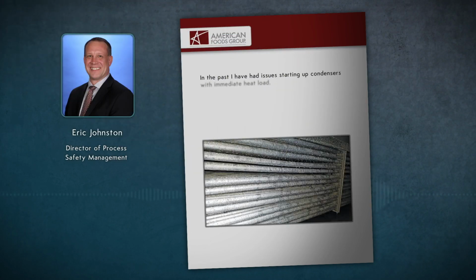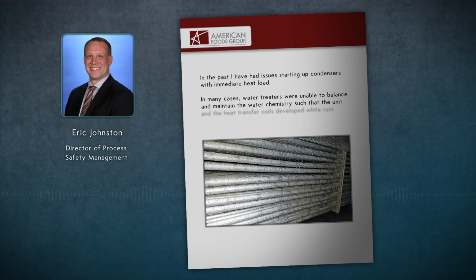In the past, I've had issues starting up condensers with immediate heat load. In many cases, water treaters were unable to balance and maintain the water chemistry such that the unit and the heat transfer coils developed white rust. White rust is a headache that I can't afford.